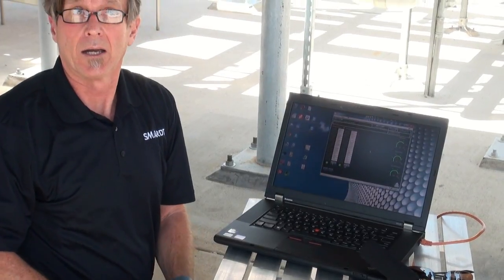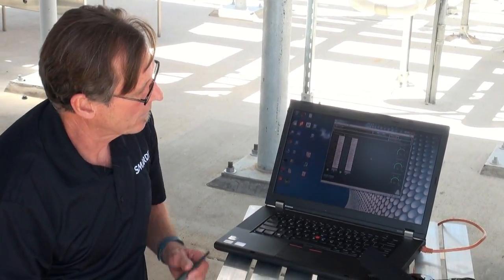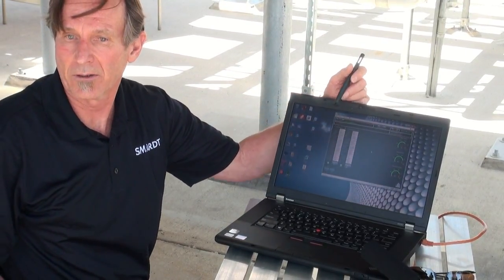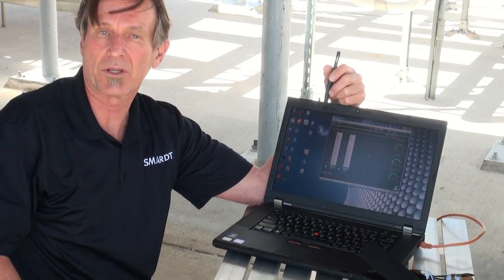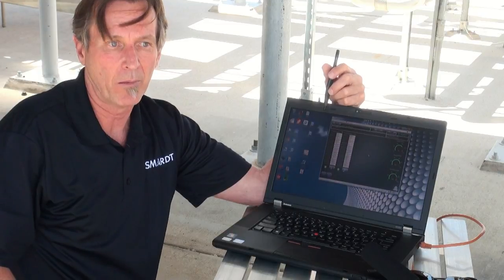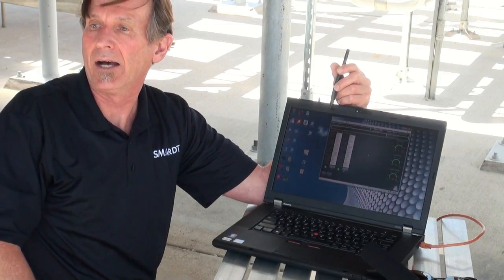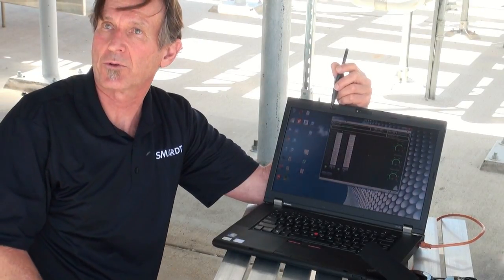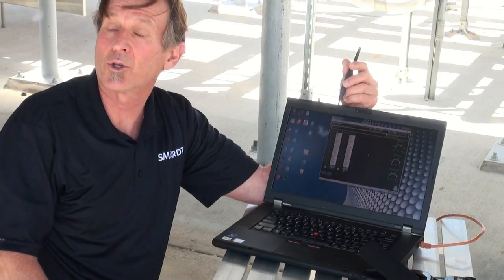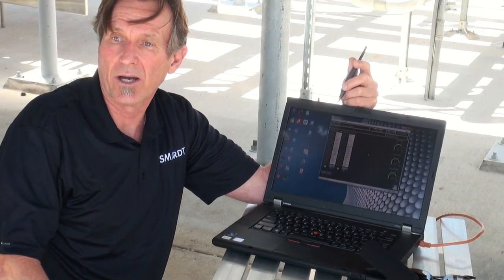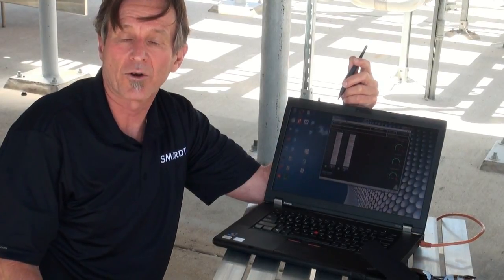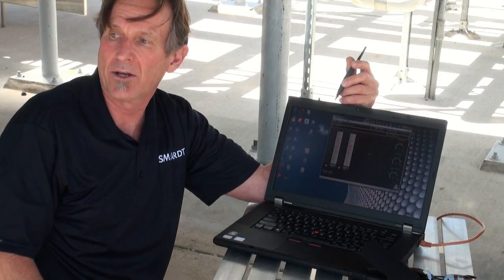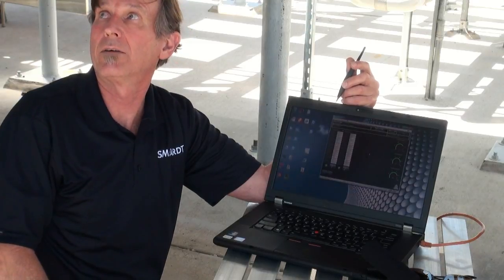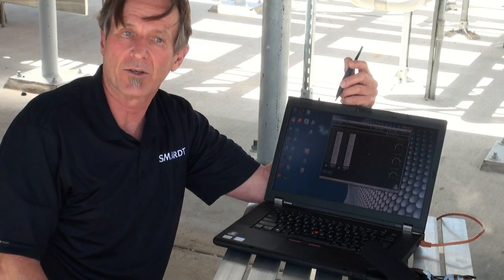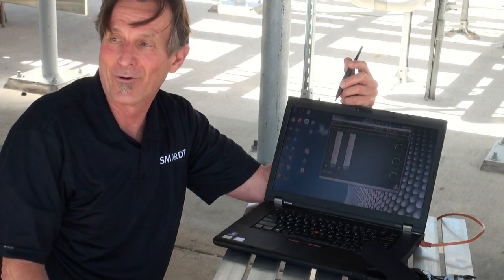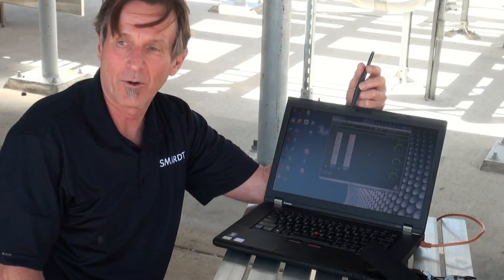Do they give you RPMs or just percentage? Yeah, our RPMs are displayed here on the compressor column, so you can see what the actual RPM is. There's a minimum RPM and a maximum RPM. Minimum RPM is our surge speed for the centrifugal compressor, and maximum RPM is the choke speed for the compressor. If you're not familiar with those terms, if you go below minimum speed, you're in danger of surging. So you'll have backward flow of refrigerant through the compressor, from the discharge to the suction side, instead of from the suction side to the discharge side, which is the way it's supposed to go. That would be a surge.